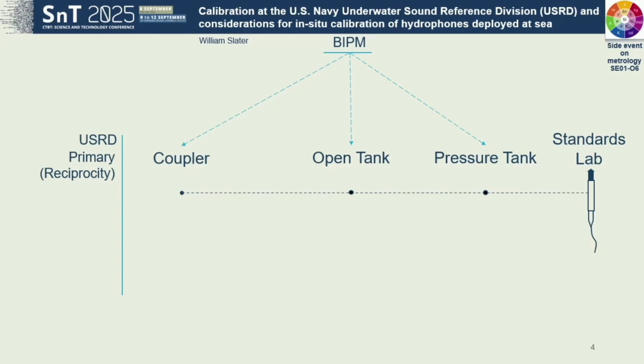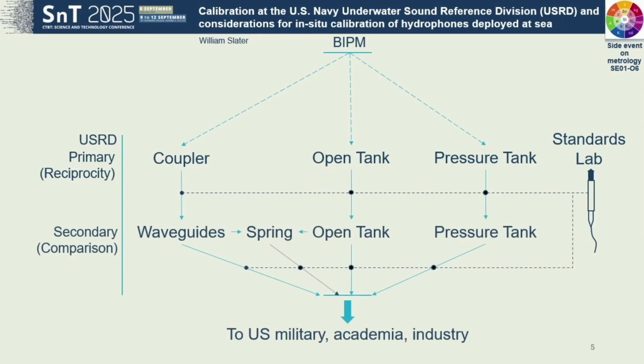Our primary calibrations provide a direct realization of the underwater acoustic Pascal, meaning they don't involve comparison to any other acoustic reference transducer. We use secondary calibrations, which involve comparisons to our primary references, to then calibrate our transducer standards in quantity, which we lease to our customers. This diagram shows how traceability flows from the International Bureau of Weights and Measures through our lab via our transducer standards.